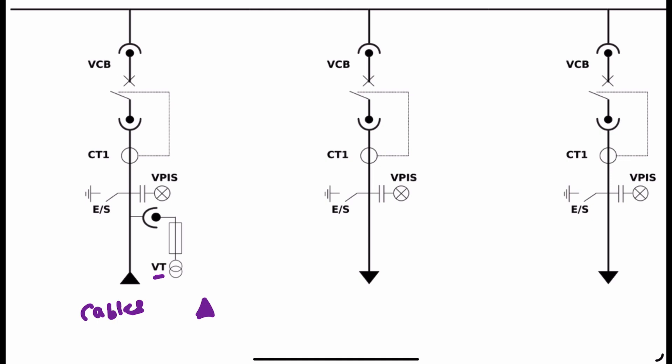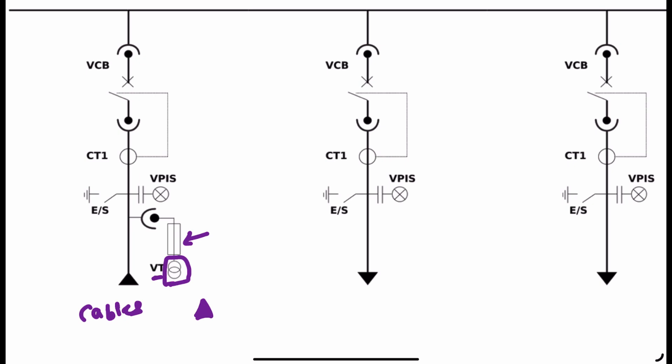Once we connect the cable, you can see we have connected a voltage transformer, which will help us in measuring the incoming supply voltage — whether the supply voltage is within the tolerance limit or not, or if it is fluctuating too much. That information we get from this voltage transformer. It also helps us provide protection when needed.